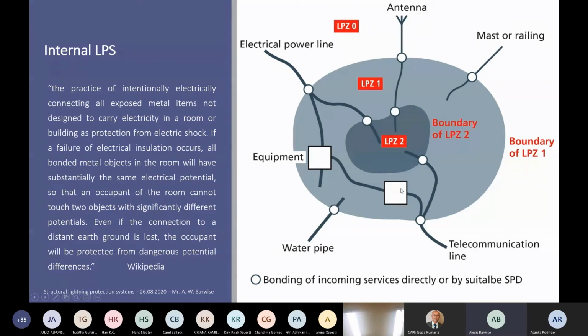And this is what we see with the drawing on the right. If we have a water pipe and we are crossing into the internal side of a building, so this light gray is the outer walls of a building, the water pipe goes in, right where it goes in, where it now can be touched, we have to bond that incoming service either directly or via a suitable surge protection device. Surge protection devices are used, for example, on the power line. If the power line comes from outside and enters the building, at the boundary wall we would insert a surge protection device to ensure equipotential bonding.